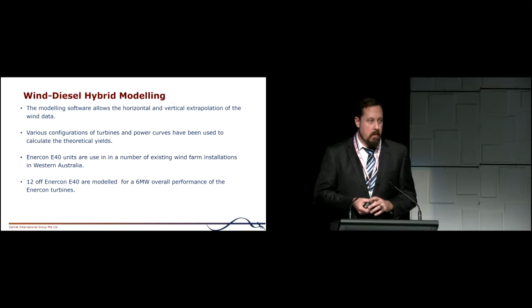For the purpose of the modelling, we're chasing 6 megawatts of power to service the plant, so we'd use 12 of the Enercon E40 in our modelling. As the diesel-fired power for our case, we had assumed some Cummins diesel generator sets, very standard for a mine of this size. And then the diesel consumption rates were put into the modelling to meet the demand of the plant's expected loads. So the no-load fuel consumption we'd used in the modelling is 76 litres an hour. This is the real key number that we are chasing going forward.